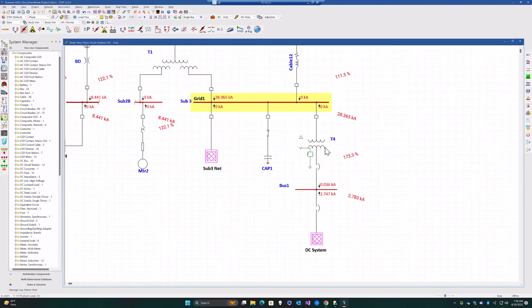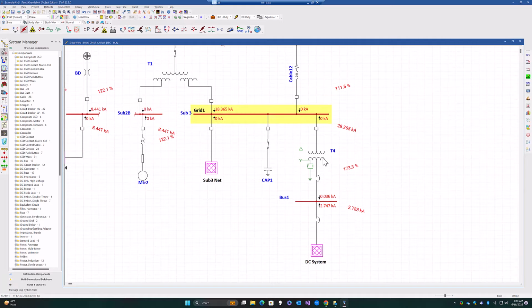And then if you want to run a simple simulation, we can go to short circuit, run the short circuit simulation, and we can see that based on the resistance and inductance that we have chosen, we are limiting the line to ground fault current to about 35 amps. So when there is a line to ground fault, there's a very low amount of ground fault current flowing through the transformer that will not affect the healthy phases, and they can continue operating as before. And that basically is a very quick simulation of the Petersen coil in ETAP 2023.